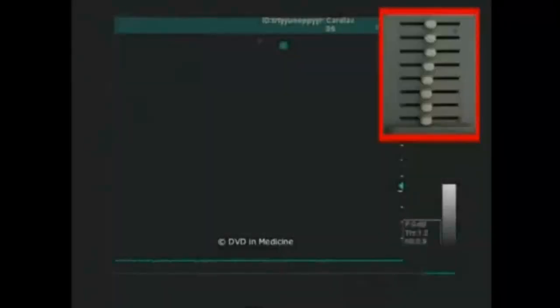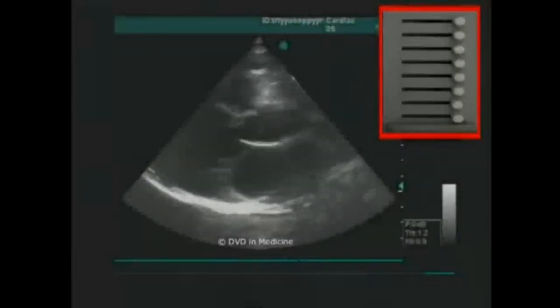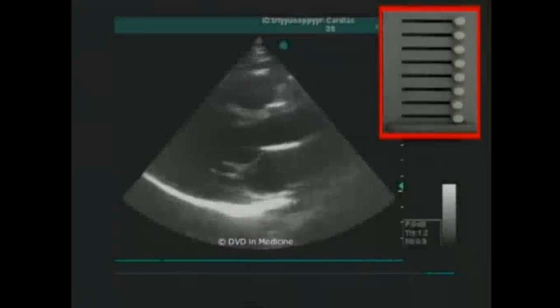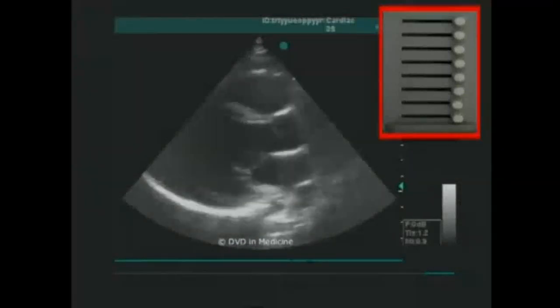In this TGC setting, one will get maximal uniform boost of signals across the whole depth of the image. In the next TGC setting, one will get a low uniform boost of signals across the whole depth of the image. The third TGC setting is optimal for the majority of the echocardiographic examinations. In this clip, we demonstrate in the real-time images the correlation between different TGC settings and final images.